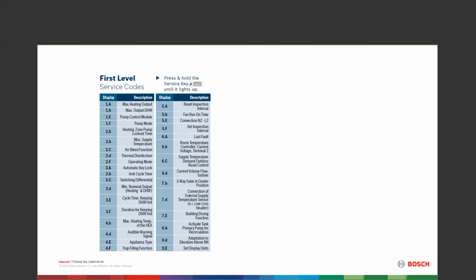2B we use quite a bit. Max supply temperature. That is your supply sensor that's on the system loop going out to the supply. The reason that we would want to limit that would be maybe a complete radiant system. We don't want it to ever go over 125 or 130 degrees, whatever you happen to want. You can lock that in and it'll stay right in there. So we lock that down to 125. We'll never see more than 125 in that floor.